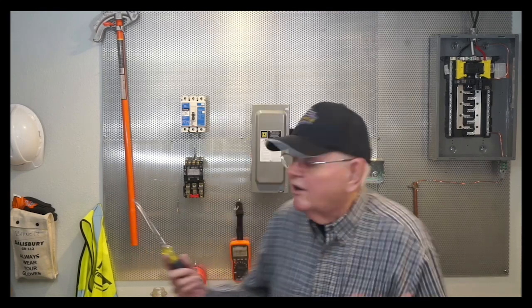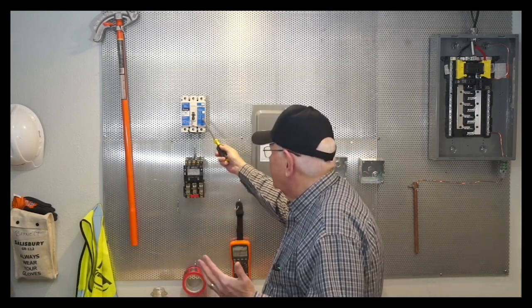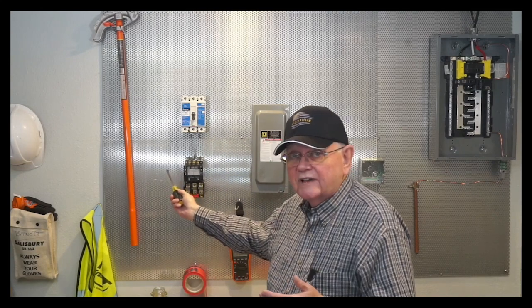One of the terms that we run into a lot in the world of motor controllers is combination starters. And people say, oh, it has to have fuses. You got to have a disconnect switch or whatever it is. And the answer is, well, no, not really. You don't find all of this information in the NEC. But there are different types of motor starters. This is an older style because I have the circuit breaker and then I have the motor starter down below.